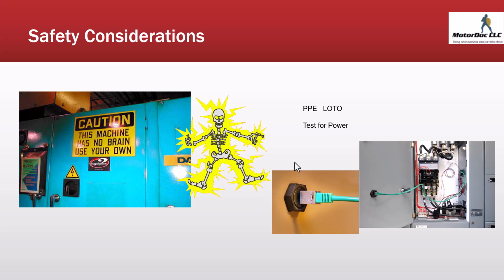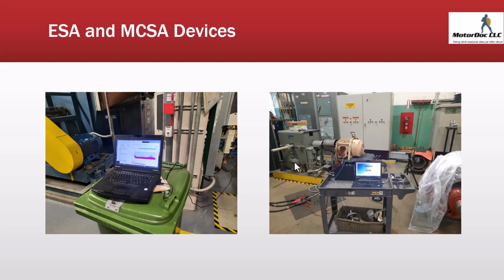Always remember, when we're going through this, we're collecting data off of equipment. So the two types of technologies we're going to talk about include, this is a current signature analyzer, single phase, and this is a three-phase voltage and current electrical signature analyzer, which allows us to look at power and so on. And this particular one here has the ability to make assumptions for power. So both of them can identify energy losses associated with each component in the machine. So we can look at things like bearing friction and stuff like that.